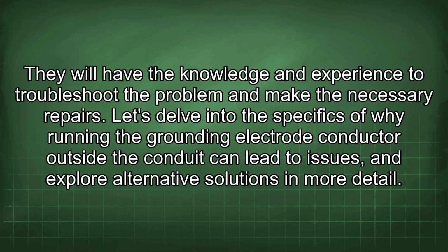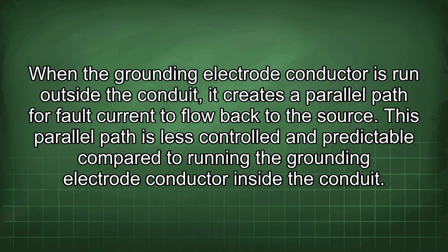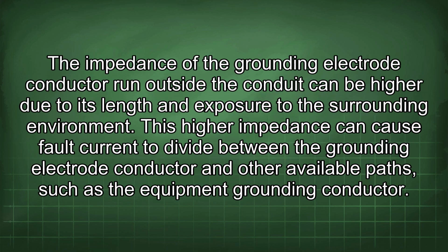Let's delve into the specifics of why running the grounding electrode conductor outside the conduit can lead to issues, and explore alternative solutions in more detail. When the grounding electrode conductor is run outside the conduit, it creates a parallel path for fault current to flow back to the source. This parallel path is less controlled and predictable compared to running the grounding electrode conductor inside the conduit. The impedance of the grounding electrode conductor run outside the conduit can be higher due to its length and exposure to the surrounding environment.